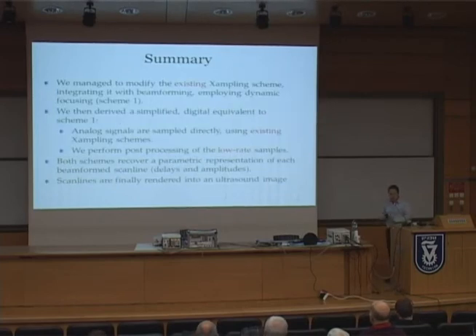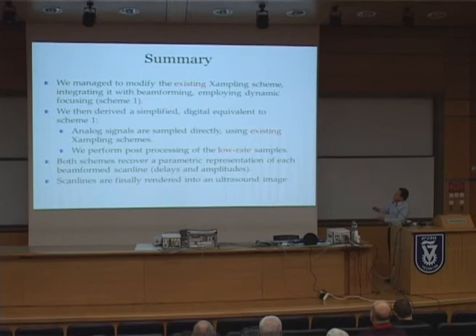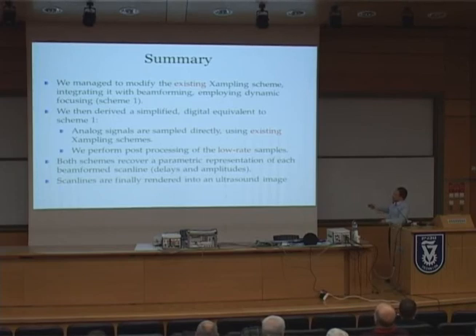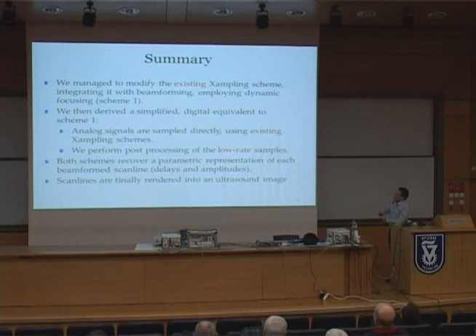To summarize what we have seen: we managed to modify an existing Xampling scheme so that it integrates the beamforming and dynamic focusing process inside it, and we derived a second simplified digital-equivalent scheme where analog signals are sampled directly using simpler existing approaches, followed by post-processing of the low-rate samples. Both schemes recover the parametric representation of the beamformed scanlines in terms of delays and amplitudes, and we can then render these scanlines into an ultrasound image.